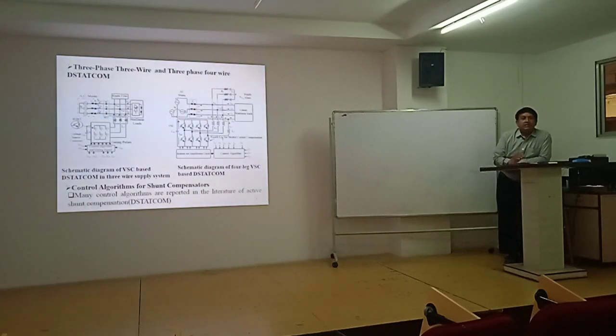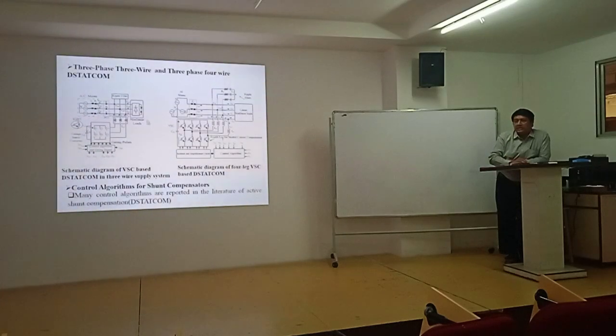Now point B. Till now I have told we want to compensate current harmonics and we are going to maintain that value less than 5% according to IEEE 519. This is one common statement. But actually, if we observe the response of this circuit more closely, in that case we have compensated, but on the other side, this harmonic is going to shift towards some other parameter. So on one side we are telling we have compensated, but we are not really compensating. We are shifting harmonic current to voltage. If we take the case without compensation with this non-linear load, supply voltage harmonic is how much? 3%. Current harmonic is how much? 25%. Clear? Without switching on this system, this is also switched off only.